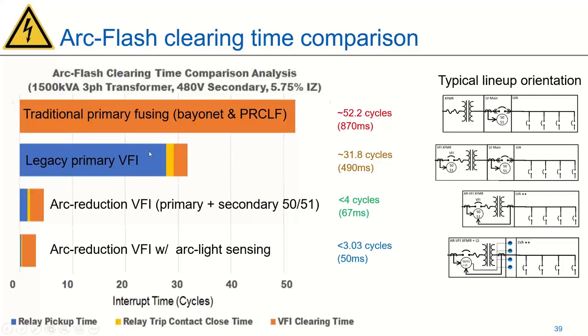So this was just to help answer that question. This was a case study done on a 1500 kVA transformer with a 480 secondary, and just the fastest we could possibly achieve, assuming it's immediately a three-phase bolted fault. Obviously, if you've got single-phase to ground faults, it might take much, much longer for a bayonet or a small fuse to react, because you've got, say, a delta-Y transformer.